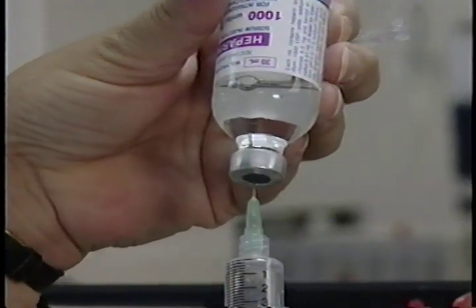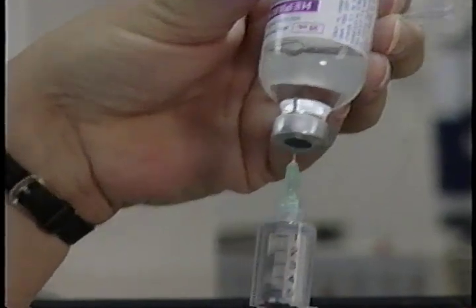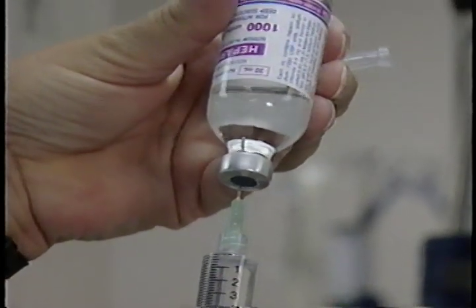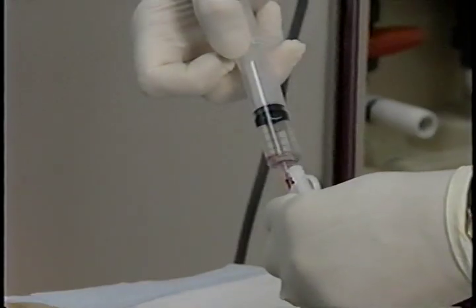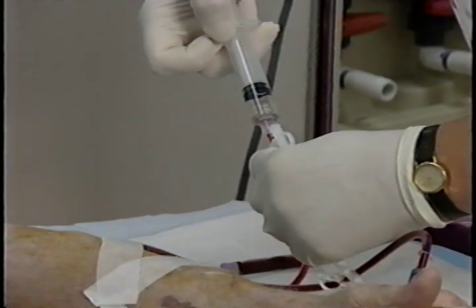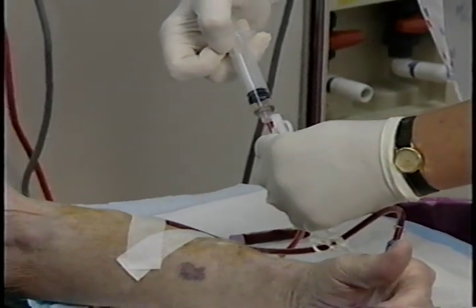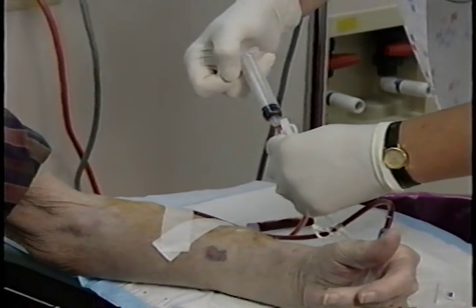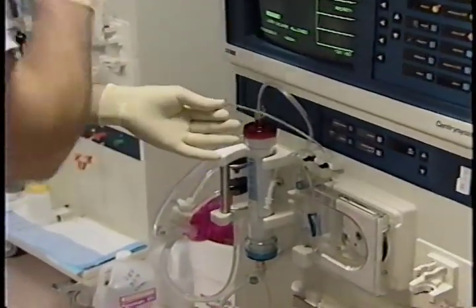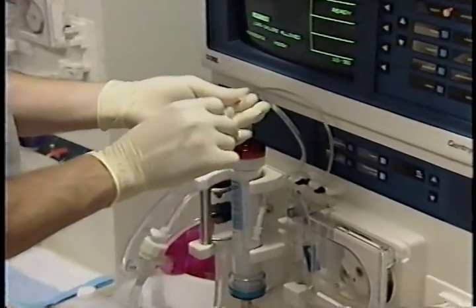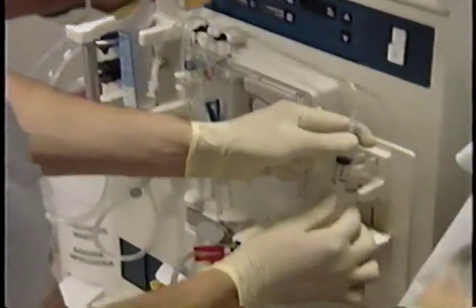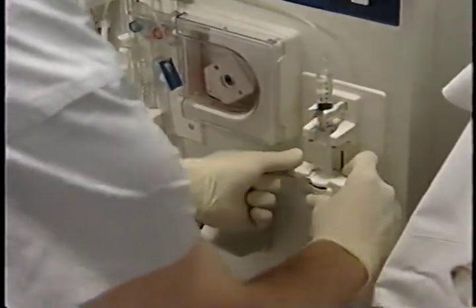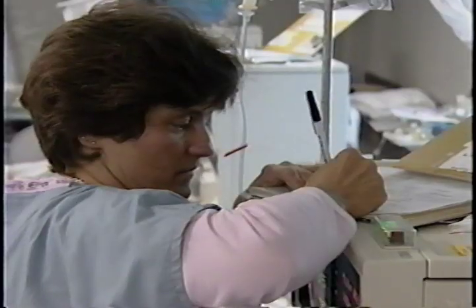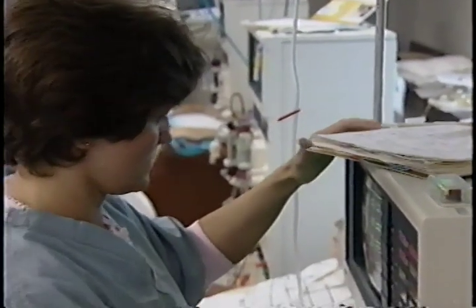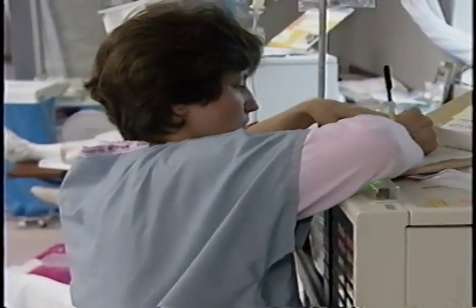The anticoagulant can be given to your patient in a single systemic dose at the beginning of the dialysis treatment, or it can be given continuously with the use of an infusion pump, or intermittently during the treatment following an initial bolus. With syringe pumps, verify that the correct syringe size is being used and that it has been loaded into the infusion pump according to the manufacturer's instructions. Each time you check your patient, you should record the dose of heparin that has been delivered.